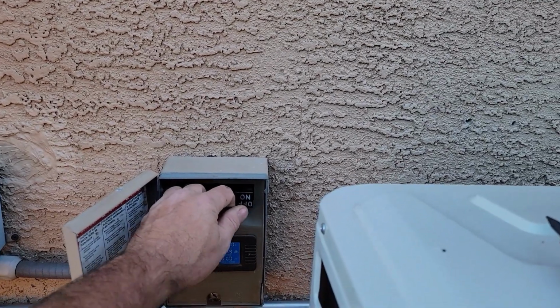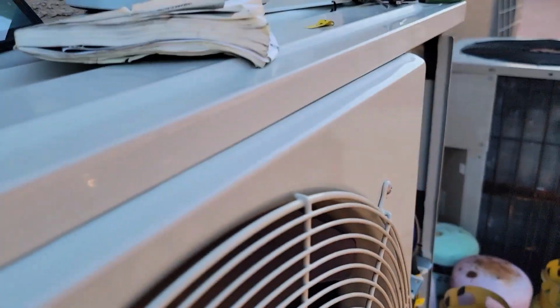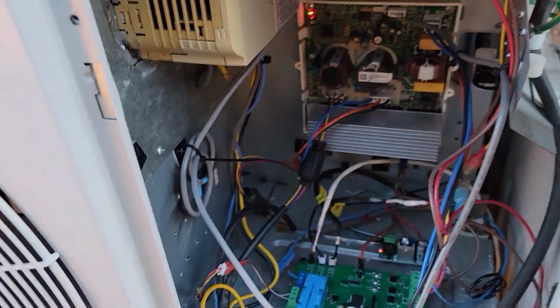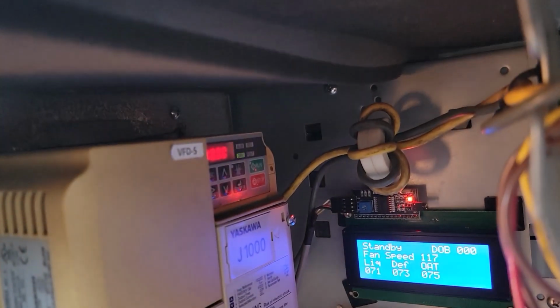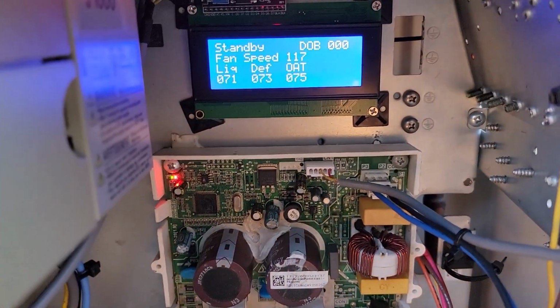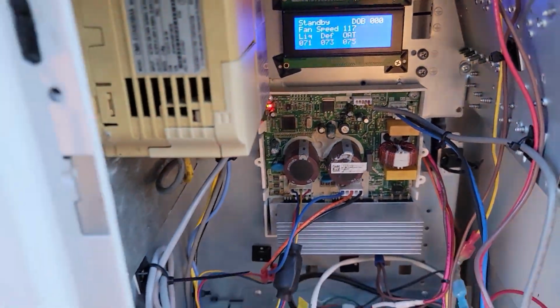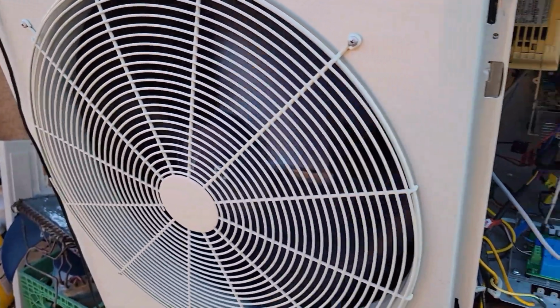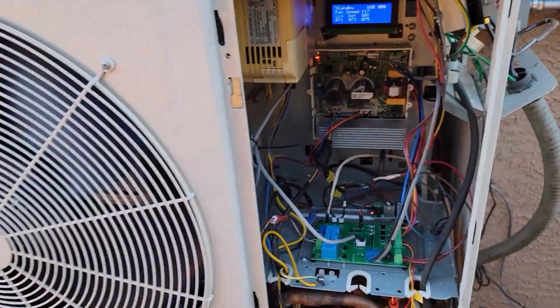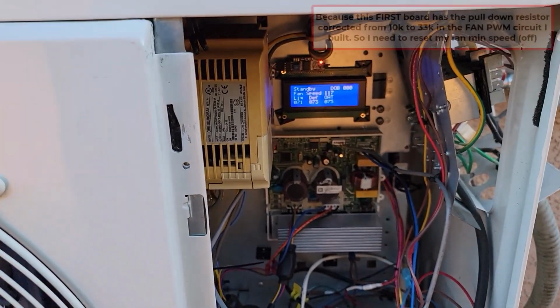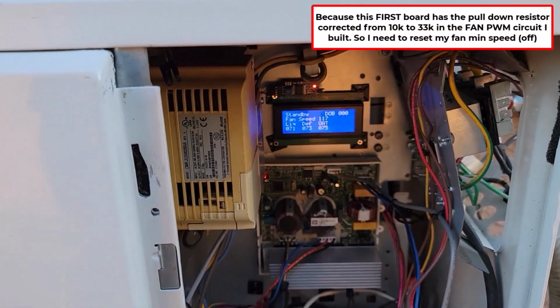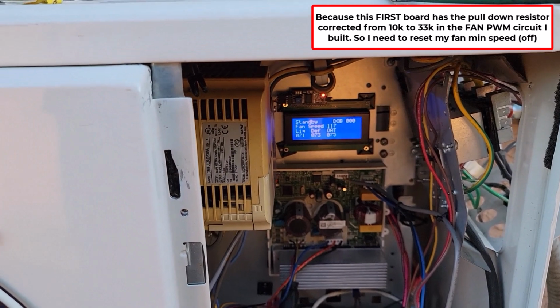Oh my goodness, this is always the part where you go 'no, dummy.' I hear the reverse valve click if they're normally closed. I see power on that, and I see pretty LEDs on that. And why is that starting? Oh, because this one has the other fan speed - I don't know why it's at 117, I've got to check into that.